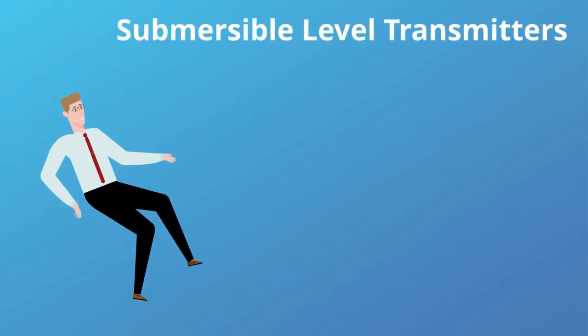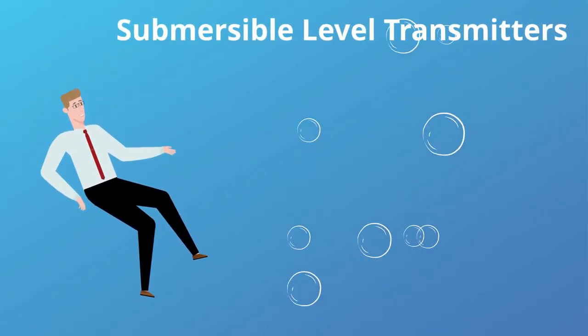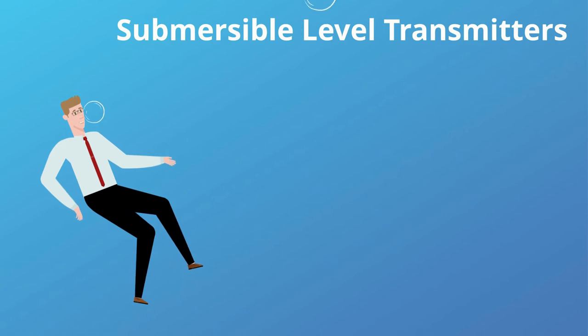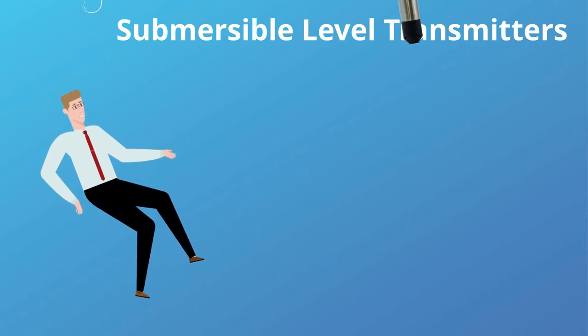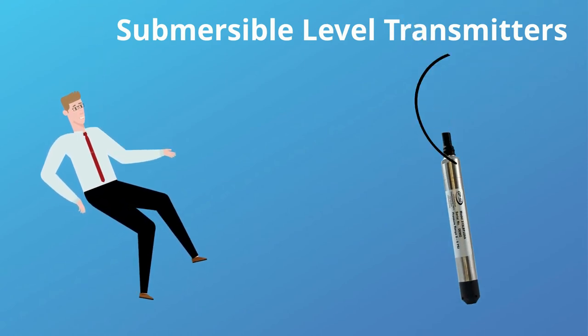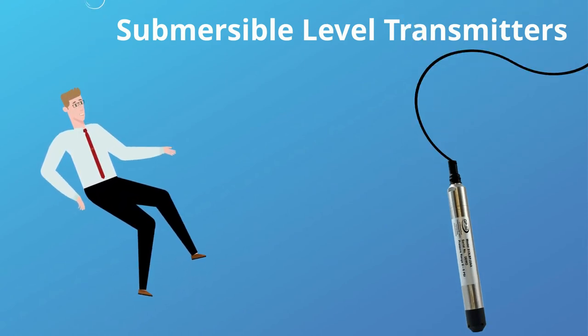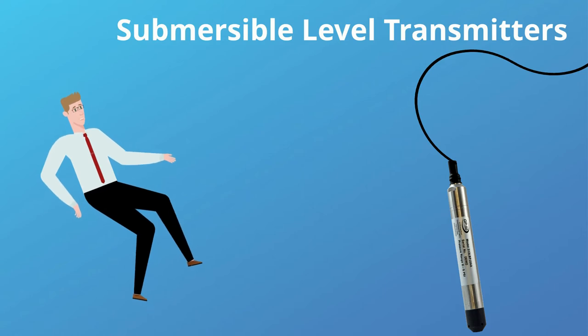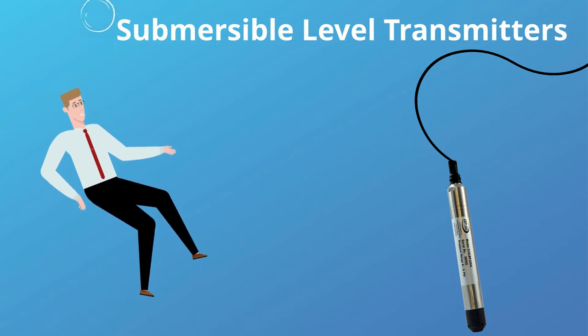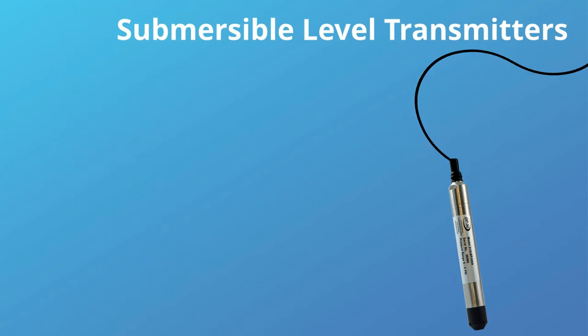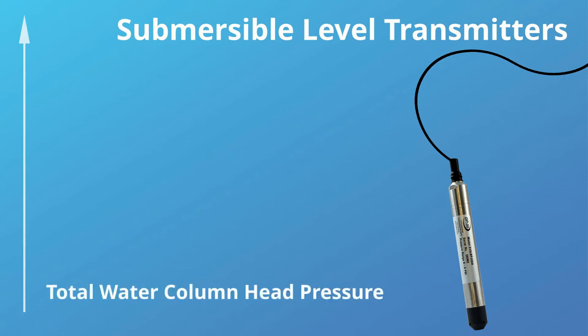Utilizing a submersible level transmitter, the transmitter is lowered into the tank or well by the connected cable down to the bottom, or just off the bottom of the tank or well floor. The distance from the sensor's face to the top of the liquid is the total water column head pressure you will measure.